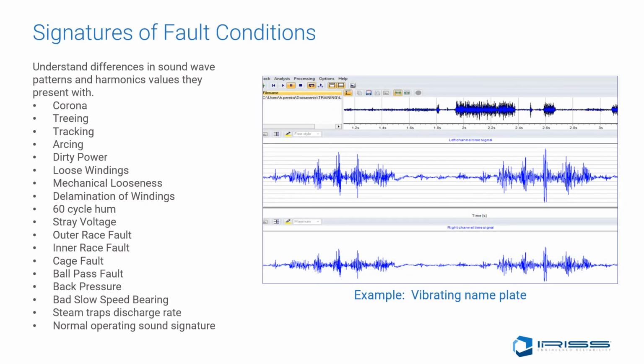In the interpretation of the sound waves, it is important to understand the importance of the sound quality for diagnosis. This includes understanding the difference in sound wave patterns of corona, treeing, tracking, arcing, dirty power, loose windings, mechanical looseness, delamination of windings, 60 cycle hum, 50 cycle hum, stray voltage, outer race, inner race faults, cage faults, ball pass faults, back pressure issues, bad slow speed bearings, steam trap discharge rate, and normal operating sounds.